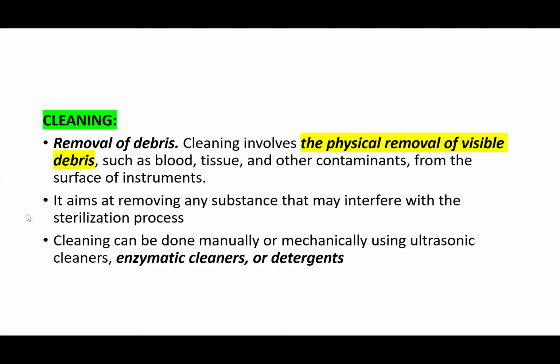Cleaning simply means removal of debris. And of course, these debris, you can see the debris. It involves the physical removal of visible debris, such as blood, tissue, and other contaminants from the surface of instruments. It aims at removing any substance that may interfere with the sterilization process. Because if these debris are not removed, it may interfere with proper sterilization of your instrument. Now, this cleaning can be done manually, mechanically using ultrasonic cleaners, enzymatic cleaners, or detergents.